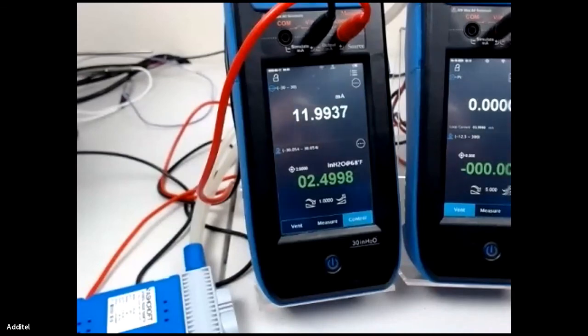The real reason we have the different models is especially on the low pressure, the inches of water — it just makes this unit really stable and good by having the additional units, so you can really control at inches of water. If you're using the 300 PSI unit, it's still pretty dang good at low inches of water, but you're not going to get the accuracy you need, probably, to do a calibration of those really low inches of water sensors. All right guys, anything else?